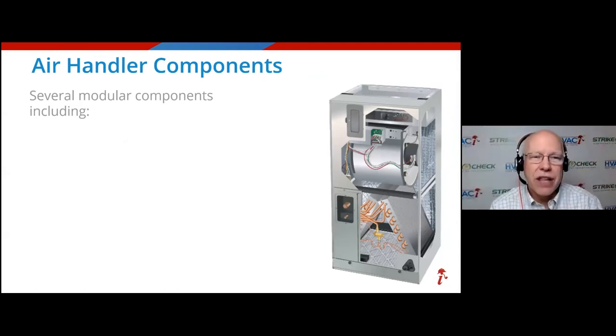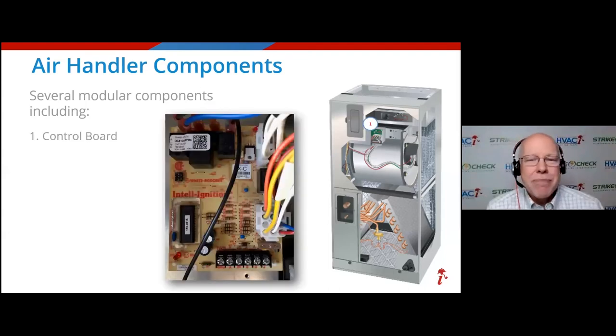And that is different, and the repairability of those two types are different as well. Cased coils are easily replaced individually. Integrated coils, not so much. All right, so that's something that might help you out. Not as many components to worry about inside, but there's definitely some. Control boards. So control boards are easily damaged by water, lightning, surge, things like that. But the other side of that is they're easily replaced, and they're available for all major brands. So if something goes wrong with this control board, we put in a new control board. You don't get a new air handler, and you don't get a new HVAC system. You put in a new control board, which is an easy repair for a technician, and get this thing running again.